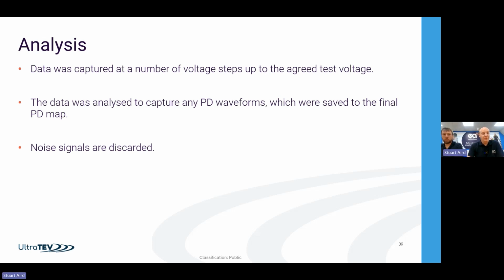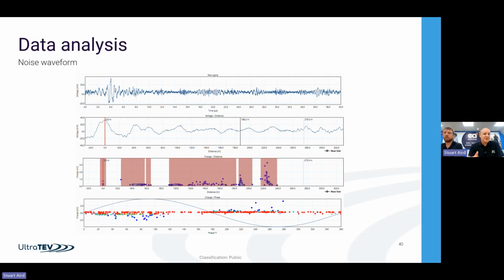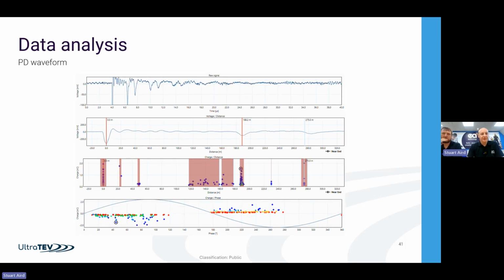And we can do this over about an hour to an hour and a half worth of testing for a cable circuit, and we focus on PD and tan delta. So we capture hundreds of waveforms during the survey, and some of them will be noise, and we see fast frequency so we can discard those, and then we want to look for the PD waveforms. These PD type ones, similar to what we were looking at before, are fast unipolar pulses, and we can look at the reflections and locate exactly, the same technology as what we're doing on the UltraTEV Plus 2.